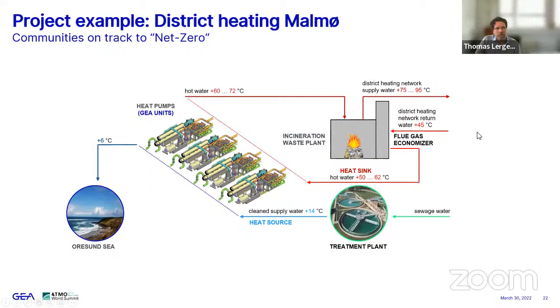On the hot side, the return temperature from the heating grid is plus 45 degrees Celsius. And because they have this waste incineration plant there, depending on the temperature requirements and the load requirements, they are preheating the heat carrier by approximately 5 to 10 degrees Celsius, Kelvin, so that the hot water is provided for our heat pumps in a temperature range of between 50 and 62 degrees Celsius. And those heat pumps don't lift the temperature that much. They lift it by approximately 10 Kelvin. So after the heat pumps, the hot water is 60 to 70 degrees Celsius warm. And then they're still leading this again through the incineration plant on a higher temperature level. They have waste heat available here to push it up to a usable 75, 90, 95 degrees Celsius.